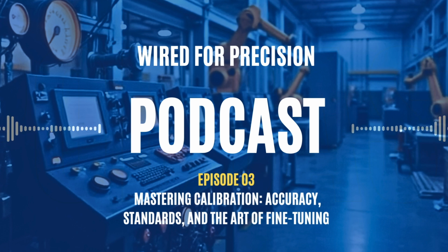Dry block calibrators. Used to calibrate temperature sensors, these devices heat up, or cool down, a metal block to a precise temperature, allowing you to insert sensors for calibration. Liquid baths. For even more precise temperature calibration, liquid baths offer uniform heat distribution, ideal for calibrating multiple sensors at once or when accuracy is critical. Pressure calibrators or deadweight testers. These are used to apply precise known pressure to test and adjust pressure sensors, transmitters, and gauges. Deadweight testers are especially useful because they're based on fundamental physics: mass, gravity, and area.